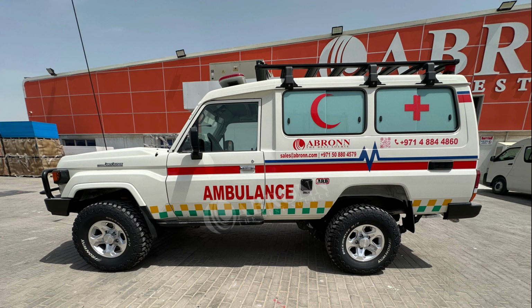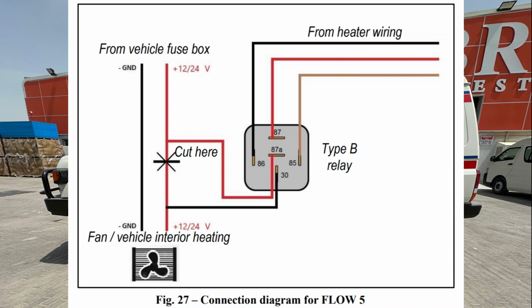If the heater is connected to an existing electrical installation, the wiring should be of sufficient diameter to prevent a voltage drop, the main cause of error 15. It is always recommended to connect the heater directly to the battery of the vehicle, vessel, or auxiliary battery. It is strongly recommended to use new and provided wiring for installation of the heater.